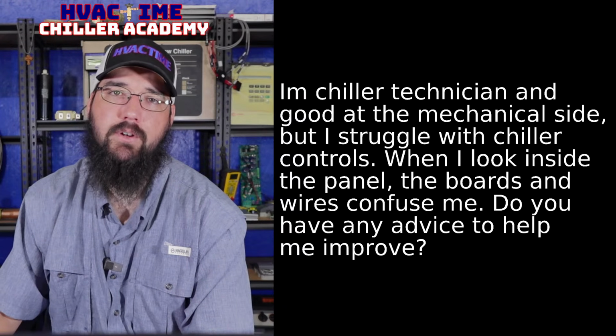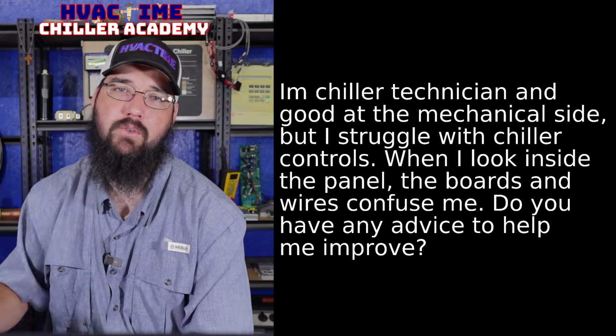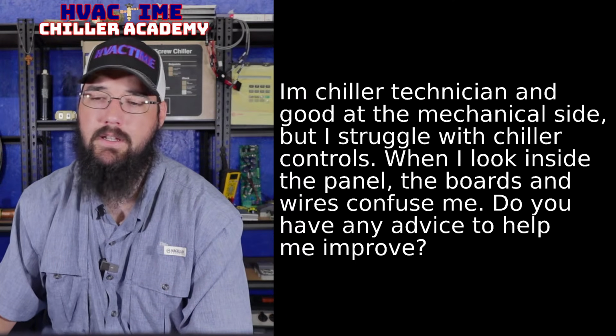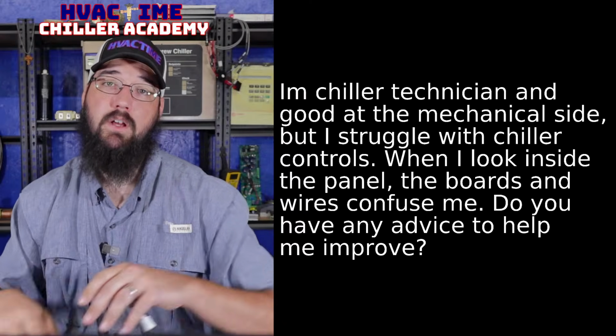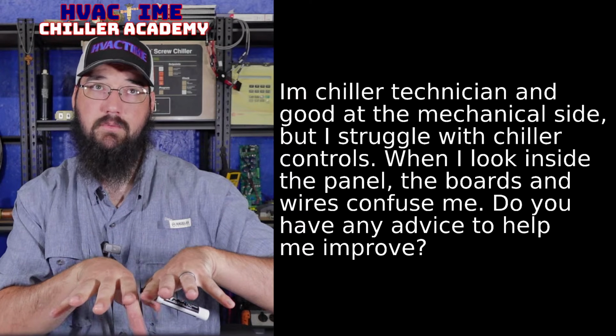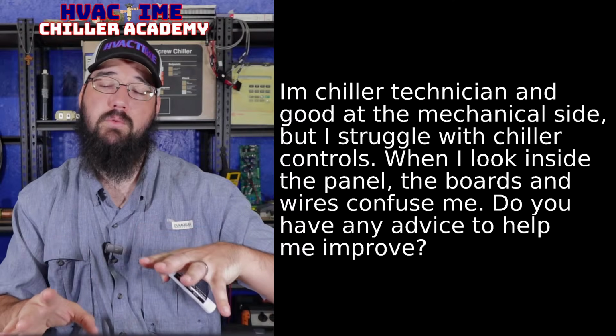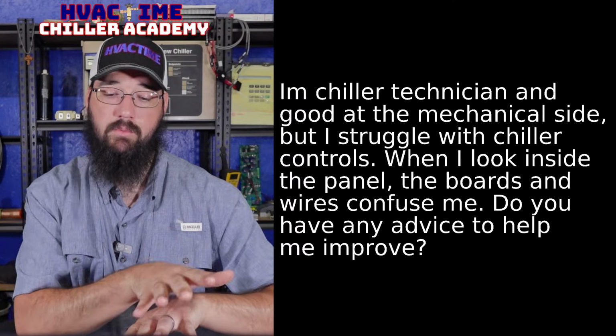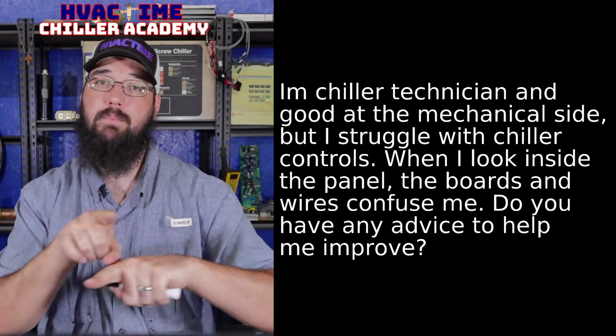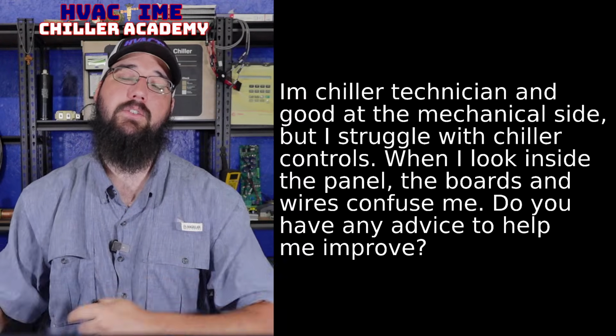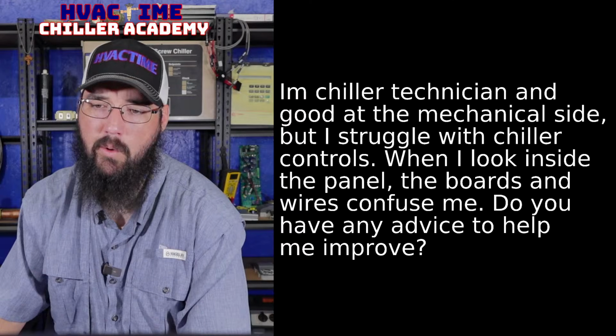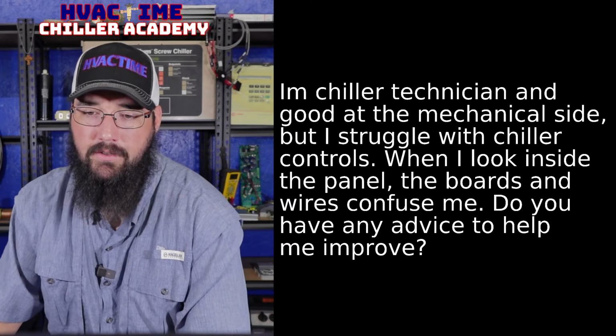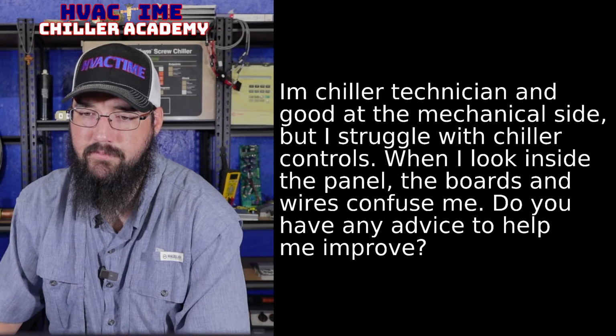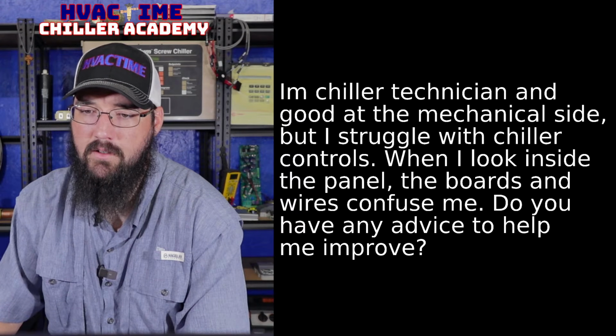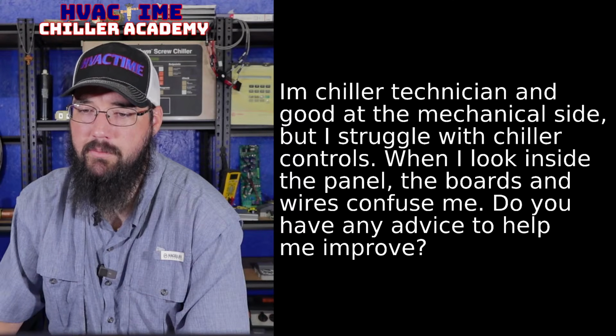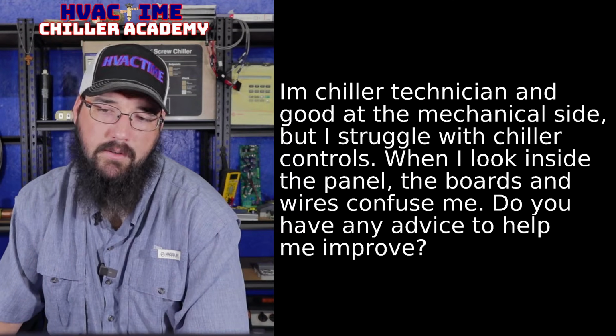It's either that or your SCRs. Those would be the primary things that, as soon as it powers up, it's going to blow immediately. It's also possible that some of those leads, they'll split them off into multiple wires, so they may have accidentally crossed a couple of wires coming from the reactor into the SCRs. So be careful, please. A lot of boards and modules communicate with the main PCB through Modbus.